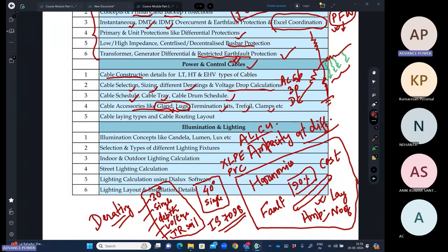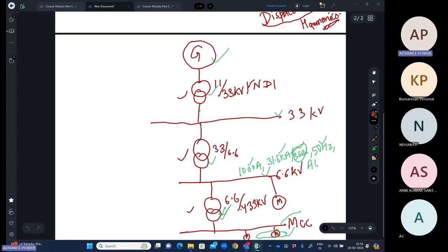What is the sheath voltage in the HV cable? How is it being minimized? How are we doing the transposition of the cable, like we do in transmission lines? So many phenomena are there in the cable itself that we'll discuss in the cable classes. I will give you the cable sizing calculation for each level of feeders. It will be either this voltage level, which is the incomer, or a motor feeder cable, or an MV or LV cable. So different types of cables.